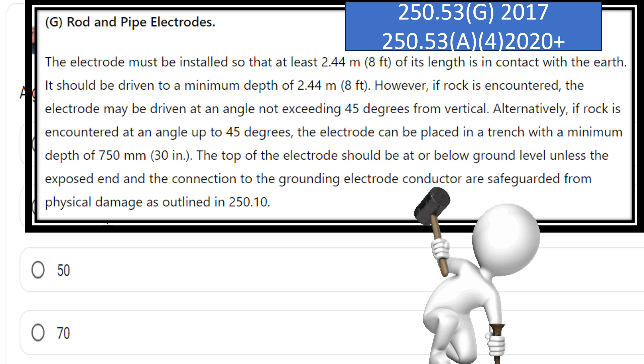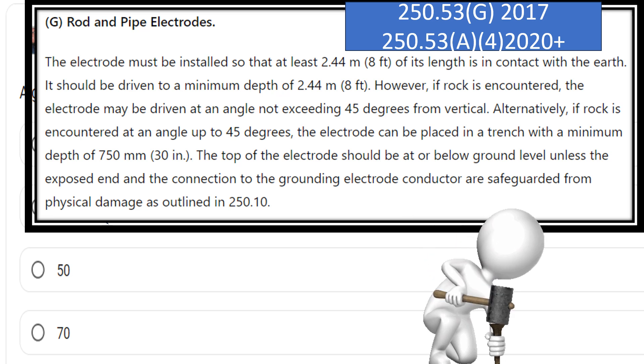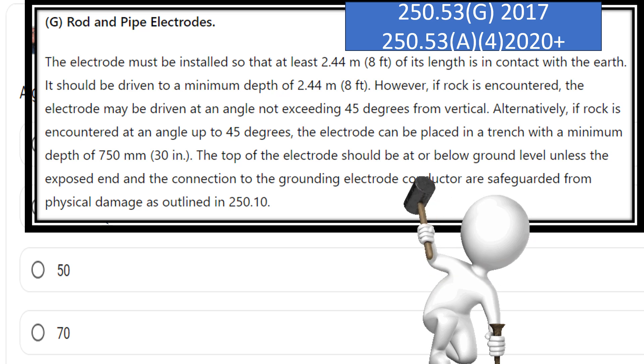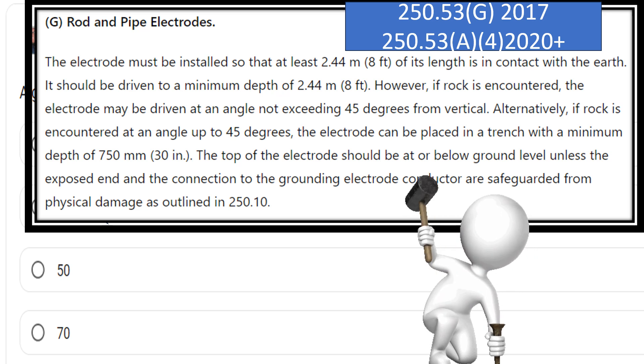Alternatively, if rock is encountered at the angle up to 45 degrees, the electrode can be placed in a trench with a minimum depth of 30 inches. The top of the electrode should be at or below ground level unless the exposed end and the connection to the grounding electrode conductor are safeguarded from physical damage as outlined in 250.10.